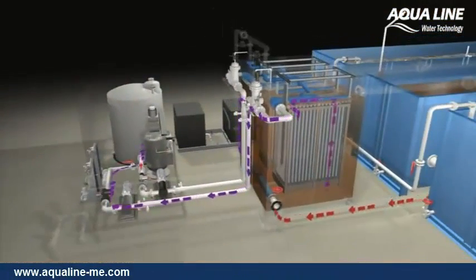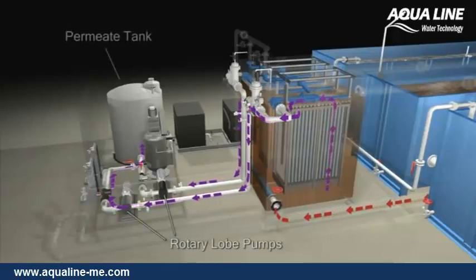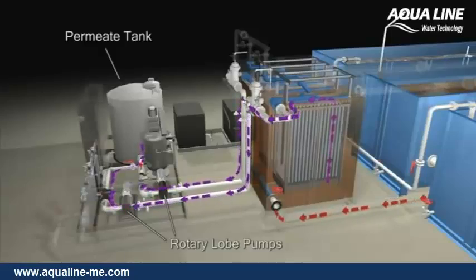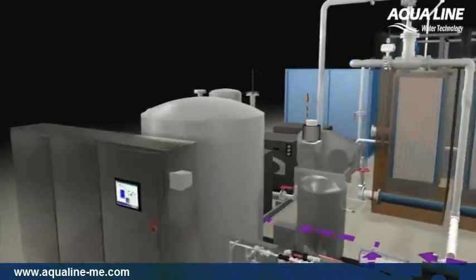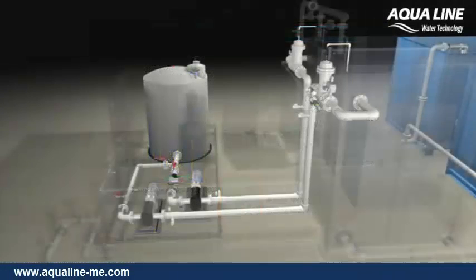The membrane system is equipped with rotary lobe pumps that create suction inside the hollow fibers and draw water through the fiber wall to the permeate collection tank. A programmable logic controller (PLC) automatically controls the filtration and membrane cleaning operations, while a human-machine interface continuously monitors system performance. The PLC is Ethernet-capable to interact with other plant PLCs or SCADA systems.